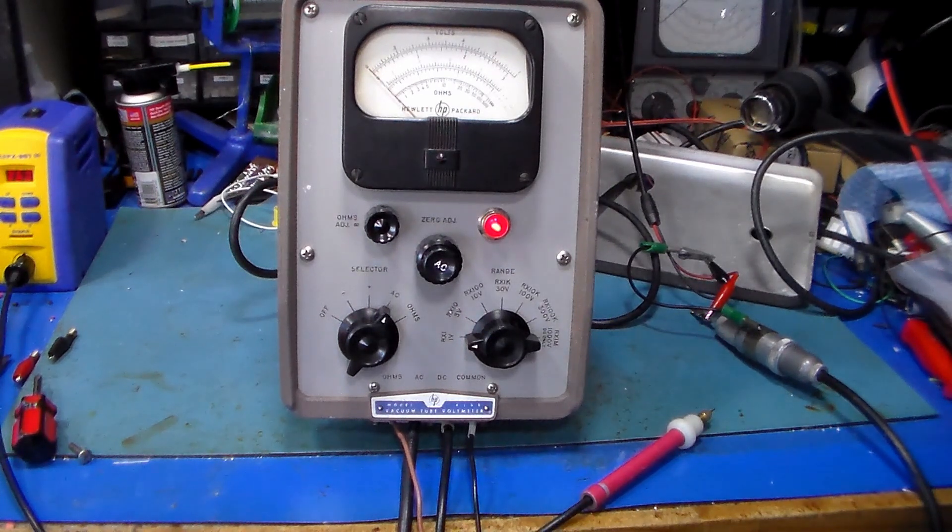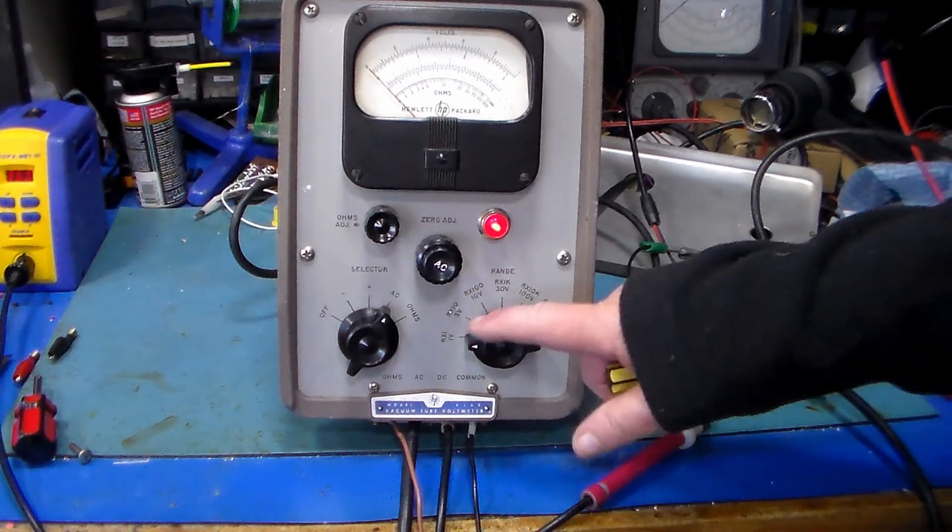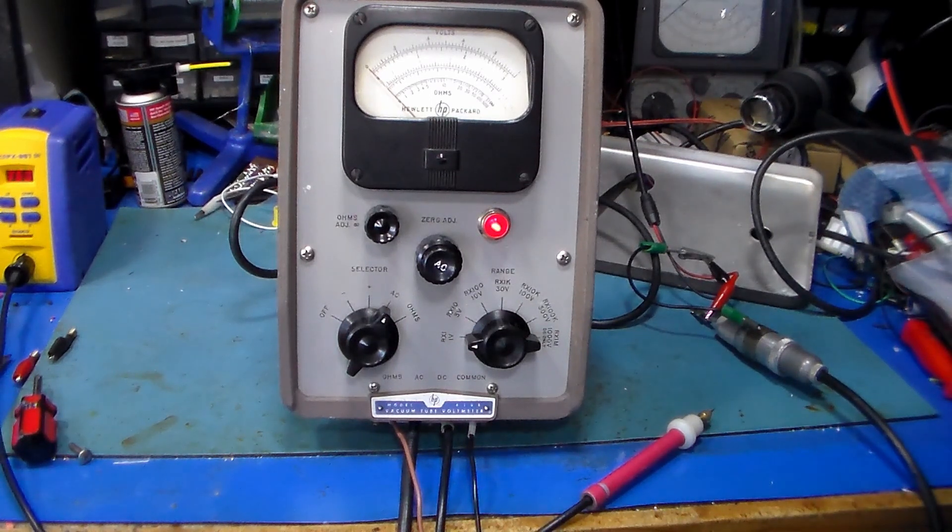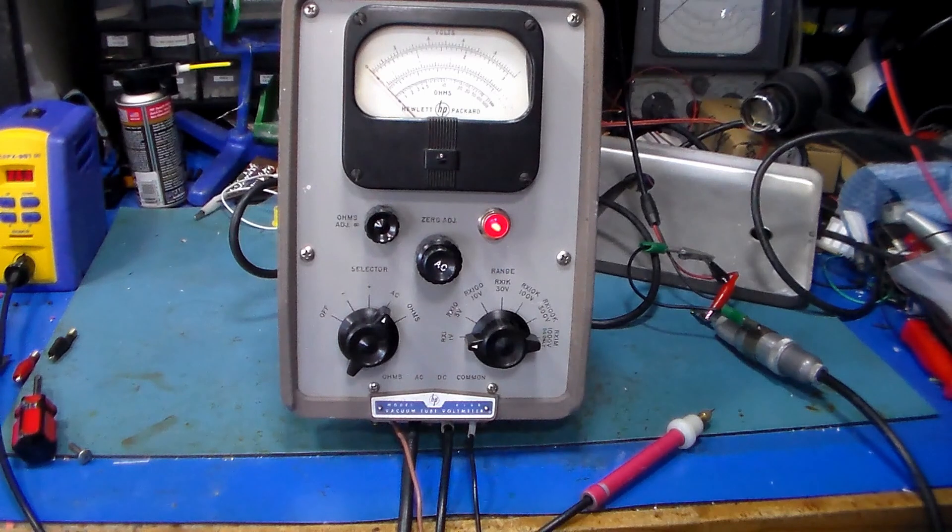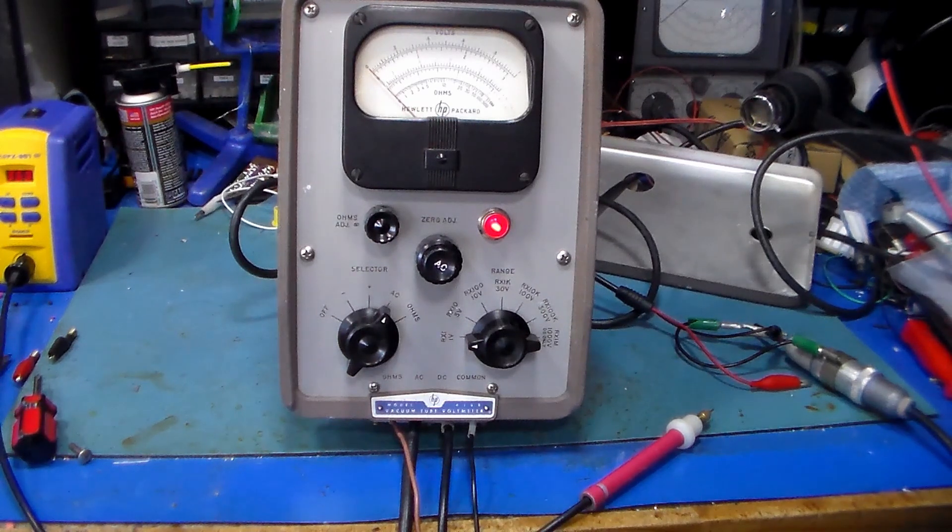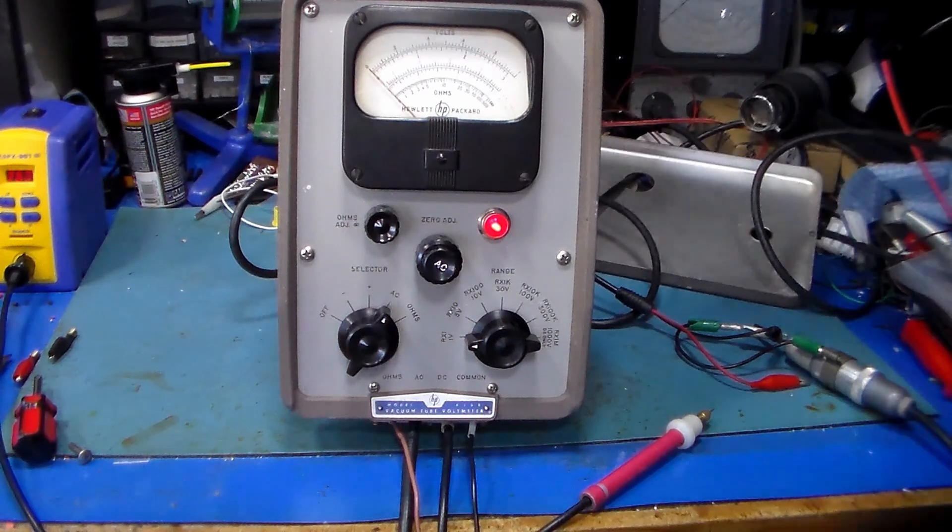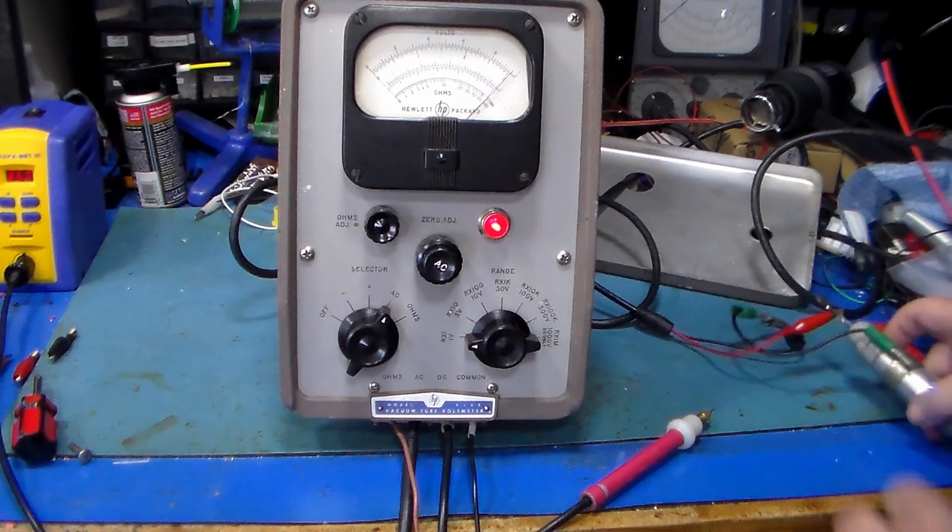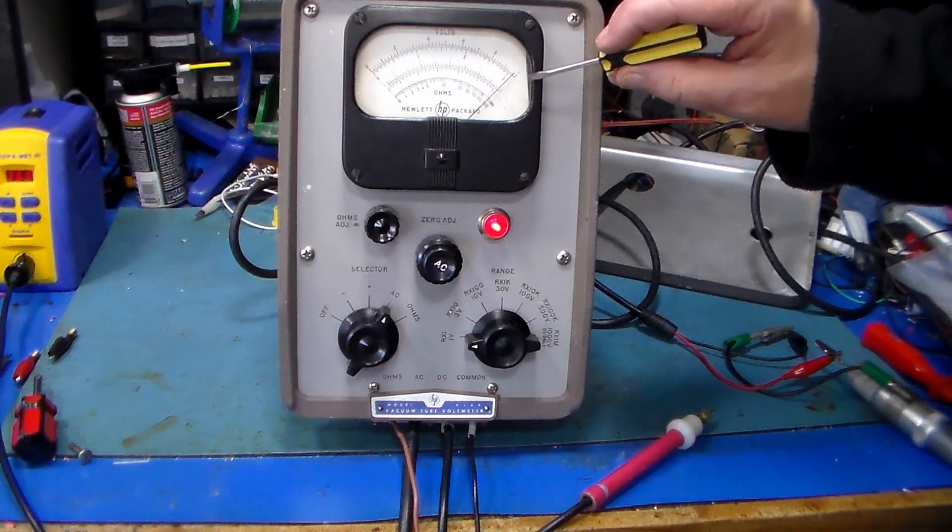After adjusting zero on the DC range, we switch over to AC and 1 volt. I've got 0 volts actually applied to the instrument. I set 1 volt output, take the short off and connect our input. As we can see, we're running just slightly low now on the 1 volt range.